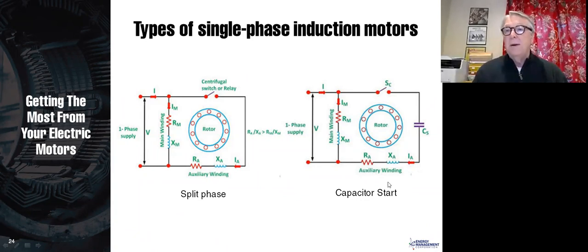Now, this is a capacitor start motor. This also has the auxiliary winding, but by using a capacitor, we get much higher starting torque. And this auxiliary winding performs much better with a capacitor on the auxiliary winding. Again, here we have the relay that's going to take out that auxiliary winding as it comes up to speed.